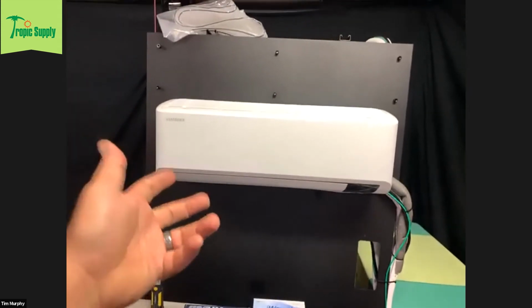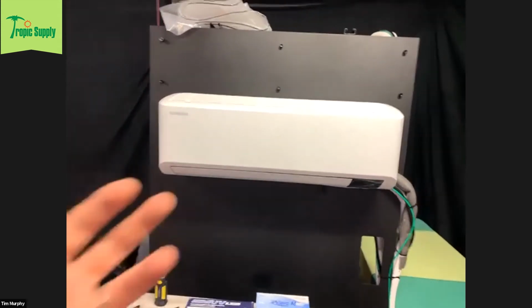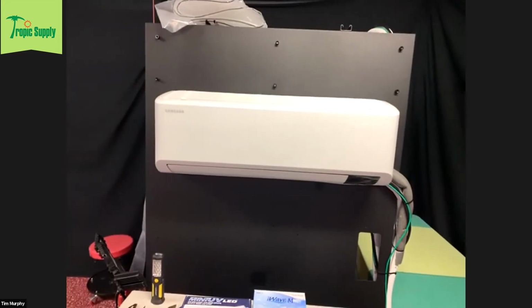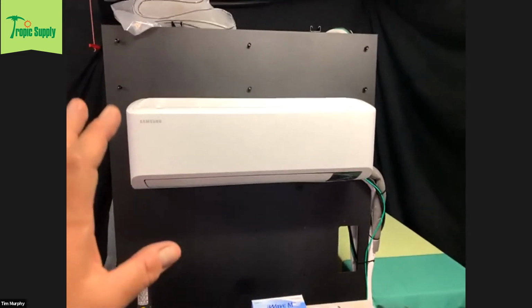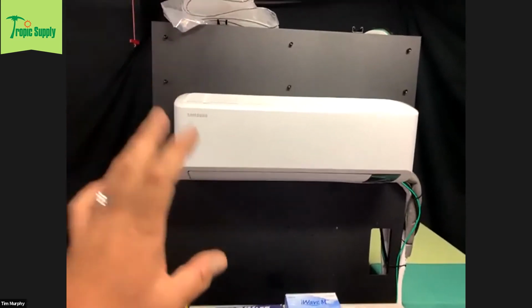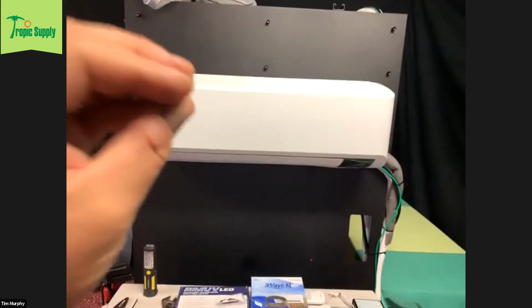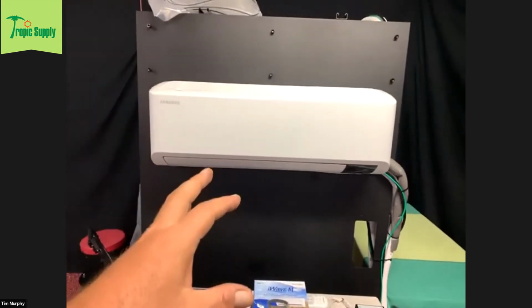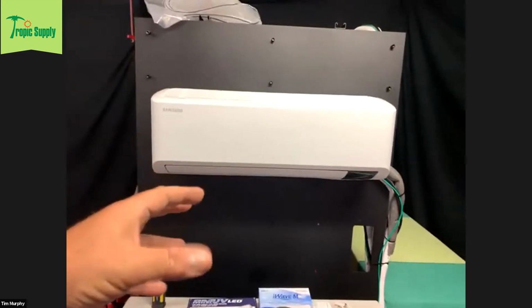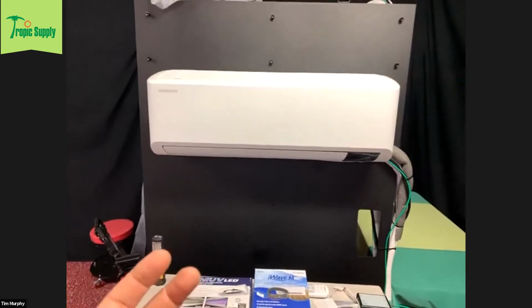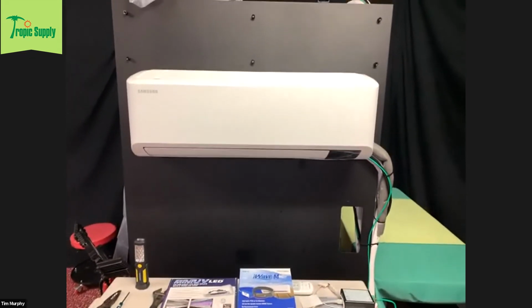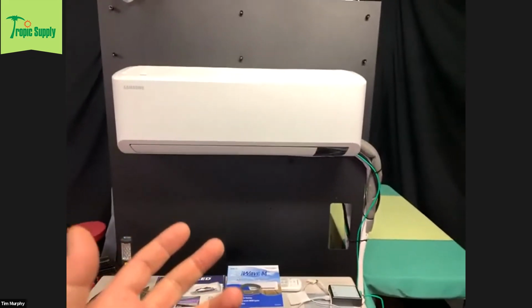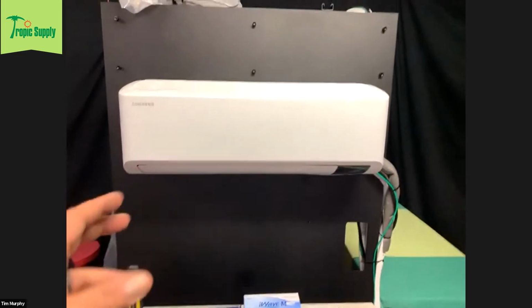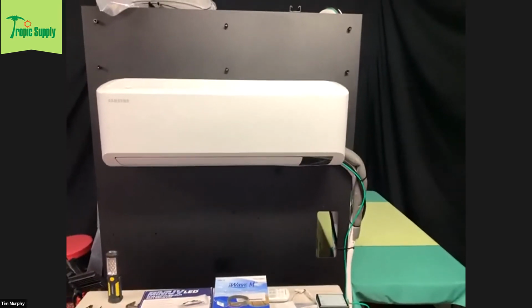After that, you pull the nitrogen out, and then you can go ahead and do a triple evac, if you're not familiar with that, look it up on YouTube. Basically, it's putting a vacuum on the system, breaking the vacuum with some nitrogen, and doing it three times, pulling it down finally to below 500 microns. That's the recommended method, but to answer the question, with Samsung you can just pump it down and you'll be good to go.